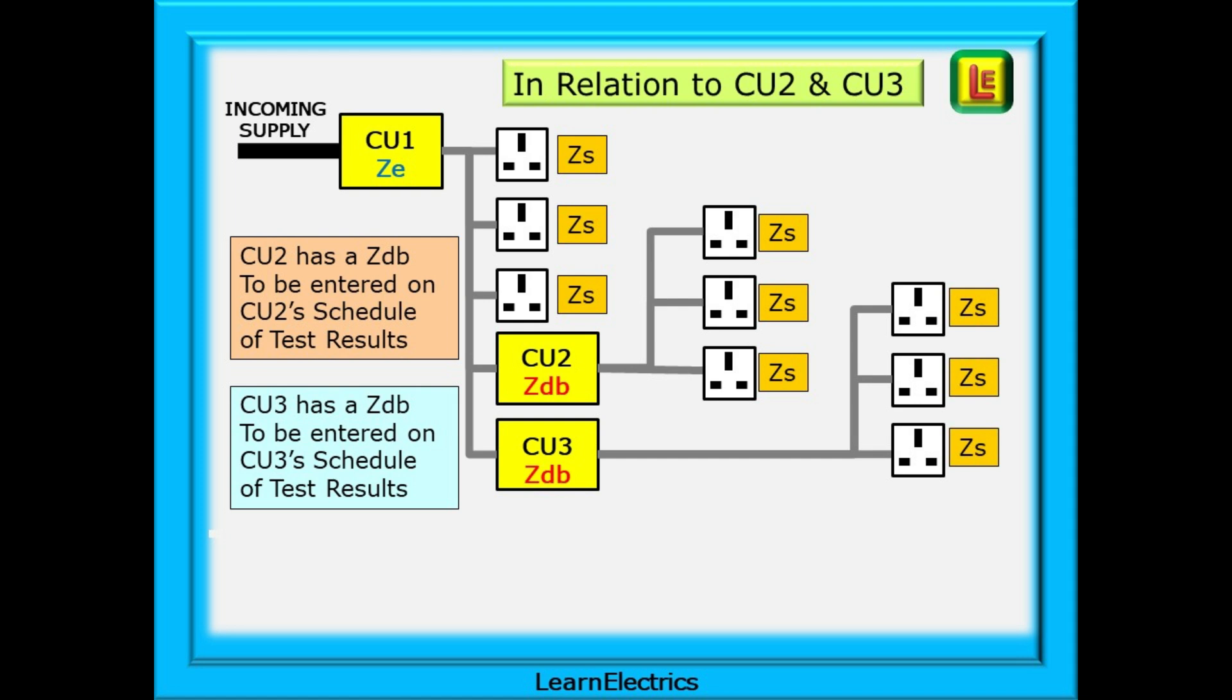Together with the ZDB, this will make the ZS for each socket circuit entered under measured ZS. Just keep track of which paperwork you are entering the data on. Be methodical. If this is CU1's paperwork, we will record CU2 as a measured ZS. If it is CU2's paperwork, then the same number is now a ZDB at the top of the test results page.